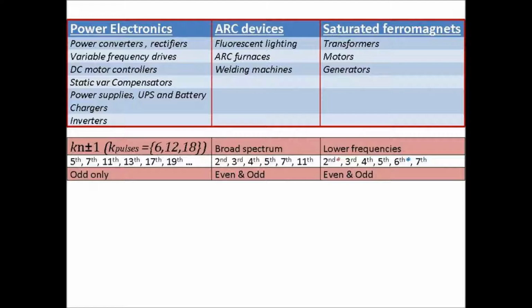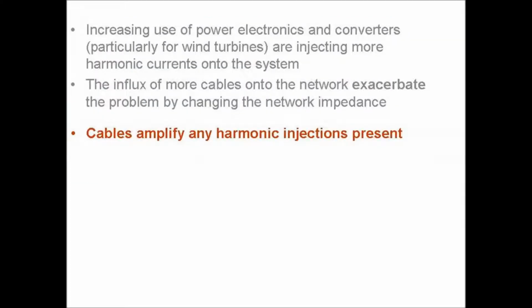Why are they becoming a concern? As I said a minute ago, the increasing use of power electronics and converters is injecting more of these currents onto the system. And because the nature of the system is changing, it's interacting with the network impedance. A lot of cables have come onto the system, and they change the network impedance by bringing resonance points down the frequency scale. What ends up happening is you can have a possible amplification of any harmonic currents that are present. A lot of people seem to think that cables are what cause the harmonics. They aren't. They're just things that can start to amplify.